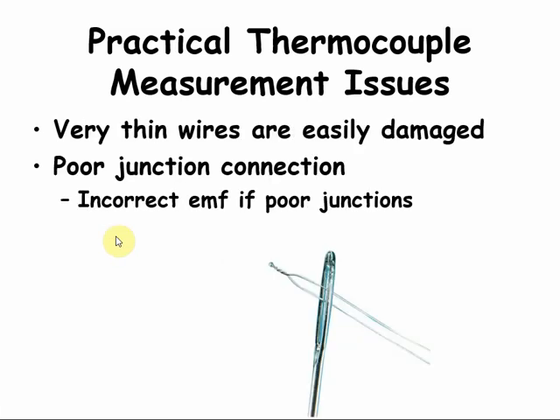The final two potential thermocouple measurement issues are listed here. If you must use very thin thermocouple wires, you must be careful to avoid damaging the wires. You might use these very thin wires if you are trying to manage thermal shunting. Finally, the last problem is a poor junction connection. You need a solid junction between the two dissimilar metals to produce the EMF. This can be mitigated by soldering or welding.